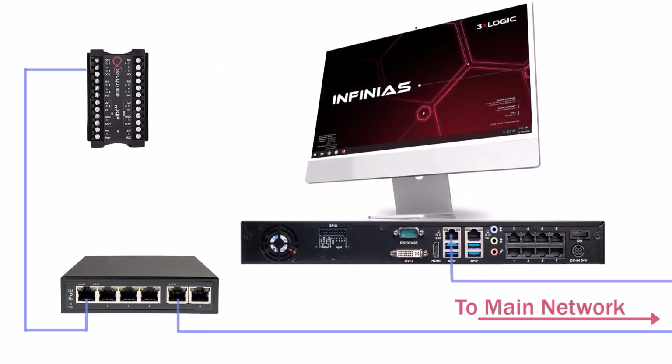Connect your patch cables as such. The EIDC will connect to a PoE switch, either the embedded switch, if available, or a standalone. The main port of the server and the standalone switch will need to be connected to the main network. Once connected, the EIDC will go through a boot process, and you are now ready to commission your controller.